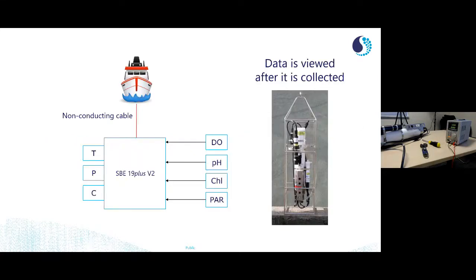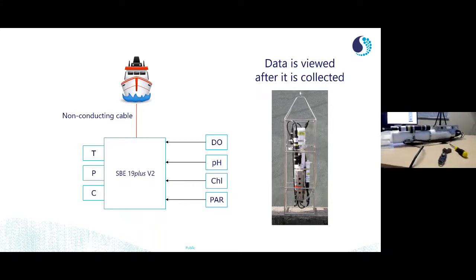With the 19 plus V2, you have a couple of options for deployment. As mentioned before, it has integrated temperature, conductivity, and pressure sensors, and you can install a handful of external auxiliary sensors. It also has its own batteries and internal memory. So if your ship or dock doesn't have a conducting sea cable, you can deploy this thing on its own, where it logs samples to its own memory. You upload those later and process them. You won't get real-time data, so you won't necessarily see thermocline, halocline, etc. But if you're just out there doing several CTD profiles, you can tie a rope to this thing and drop it in the water. That works fine.